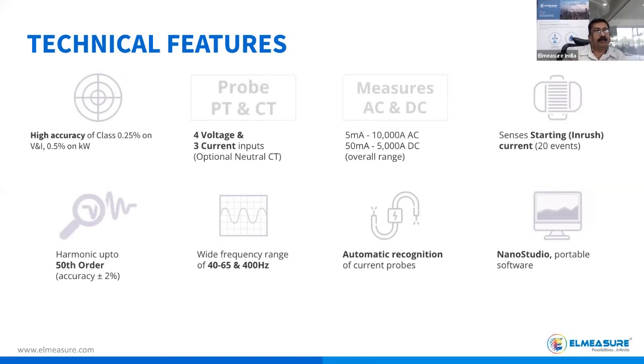When you talk about accuracy, voltage and current accuracy is 0.25 in this product, whereas in Nanoweb 1 it's 0.5. The power accuracy in Nanoweb 1 is class 1, whereas in this one it's 0.5. Coming back to the probes: 4 voltage and current, 3 current, with optional neutral CT. Quite a few places nowadays are asking for neutral CT also, so this product can measure both 3 current as well as 4 current. And like we talked about, measurement of AC as well as DC is possible in this particular product.